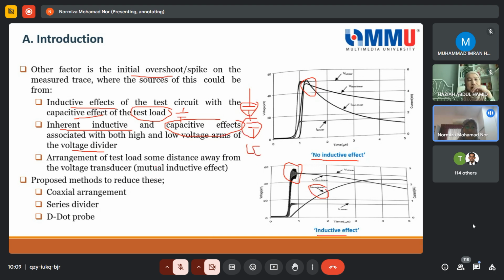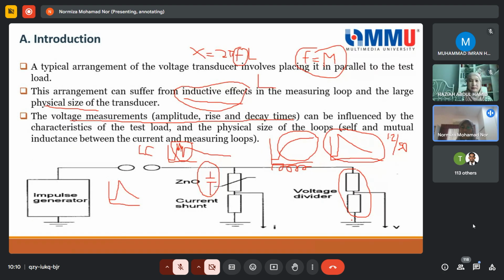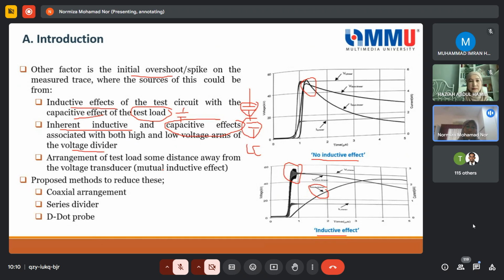So arrangement of the test load some distance away. This is also when you have some distance between the test load and the transducer, as what you've seen here. Then some distance away, especially if we run the test by field measurement, you may come across this mutual inductance, which gives you this oscillation again. So not only does the inductive effect give you oscillation, it also changes the results. In other words, you can see here the nonlinear now becomes very much delayed.